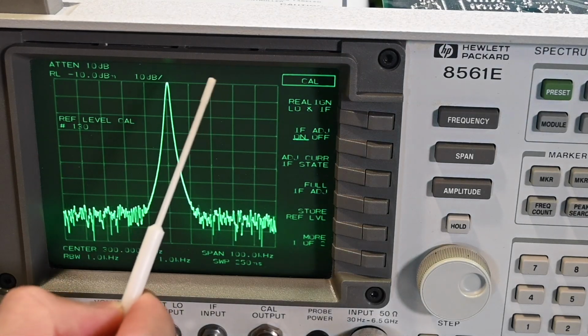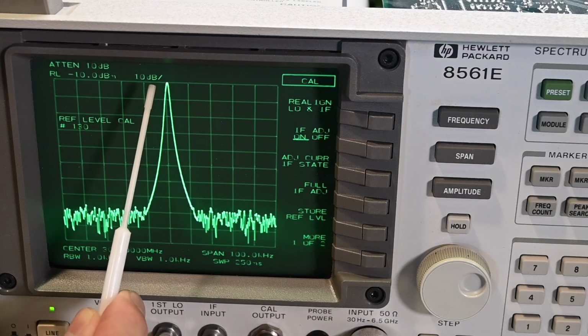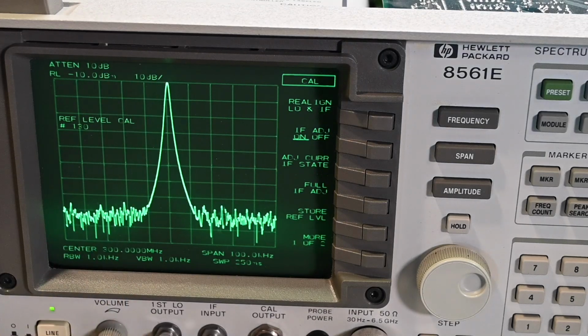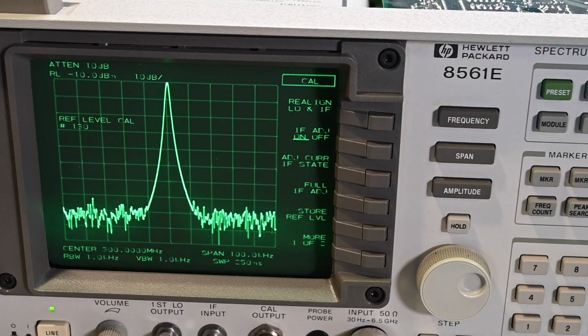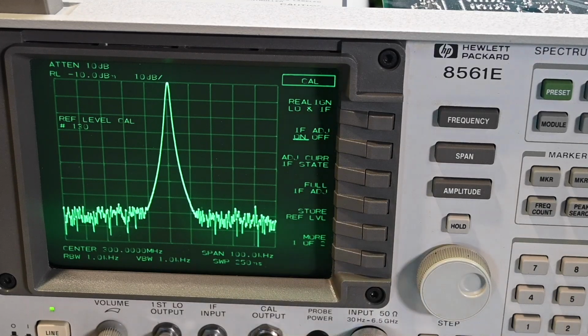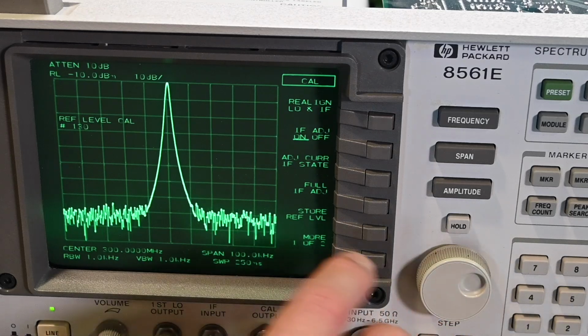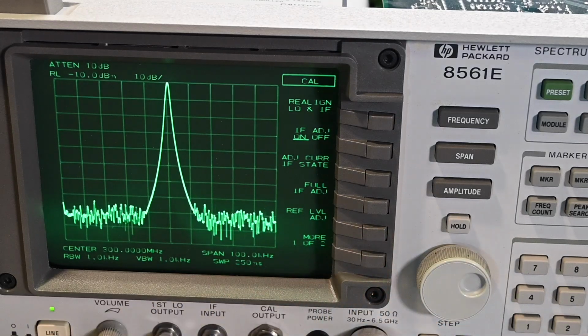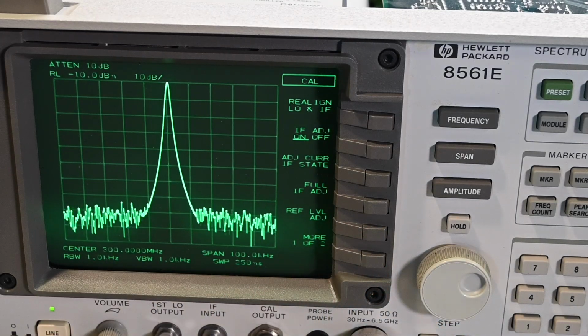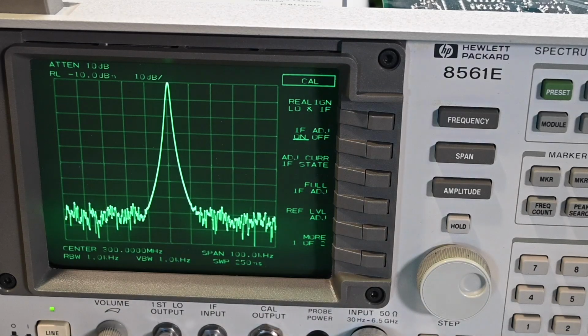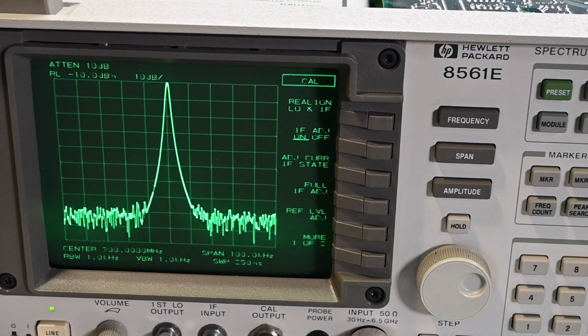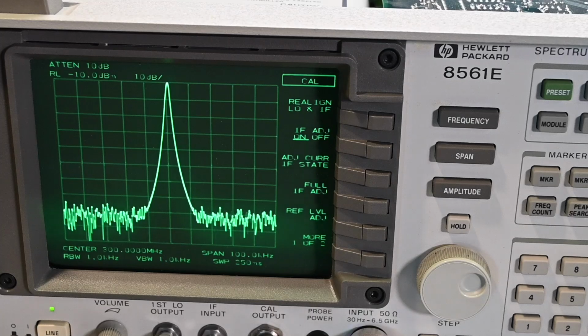So this peak right here, I think that really looks good. It's just touching that reference line right there. So I think that's right where it should be. So I think we can call that good right now. That should be acceptable. So now I just need, it says store reference level, so I want to do that. So that's now in the memory, and it will hold that for infinity until it's changed again, so no problems there. That's perfect where it needs to be.